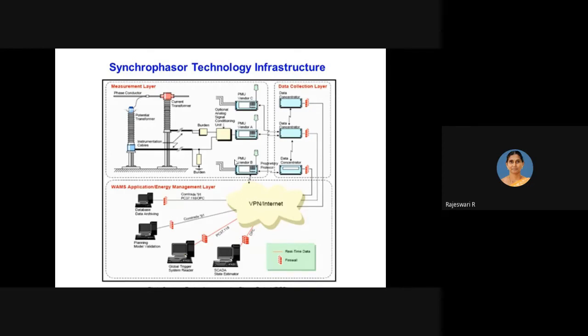So the measurement layer, as we discussed earlier, has the PMU installed there in the yard, getting information from the CT and PT and converting the acquired analog signal to phasor form. This phasor form of voltage and current signals, and other additional information derived from them, like frequency, the rate of change of frequency, and circuit breaker status, is given in a particular data format and transferred through Ethernet to the data collection layer. And from this data collection layer, it is given through the internet to the next hierarchical level, for application purposes.